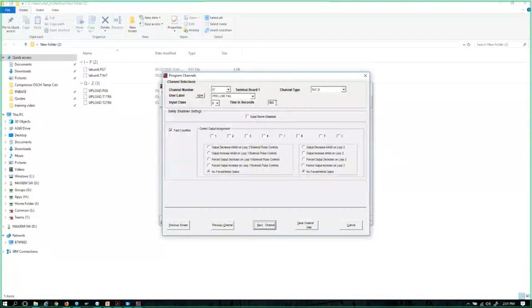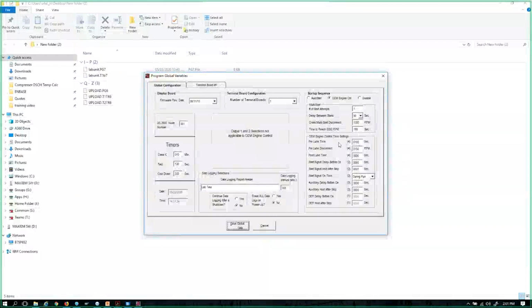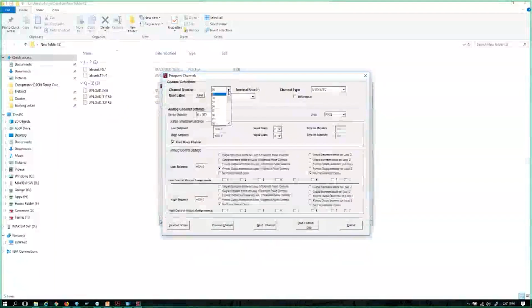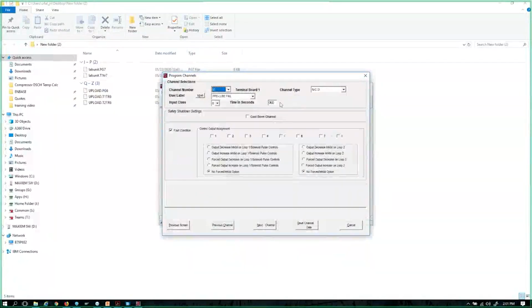And so I told you earlier on the global configuration page, I had a way to not really worry about that prelube fault. Remember the prelube fail event? I said, put this at a greater number than the time to reach 350 RPM, because we don't want to see a prelube fault here. We want to see an overcrank issue here. But if we jump back over to page 7, we can see we had a different way to trigger a prelube fault.